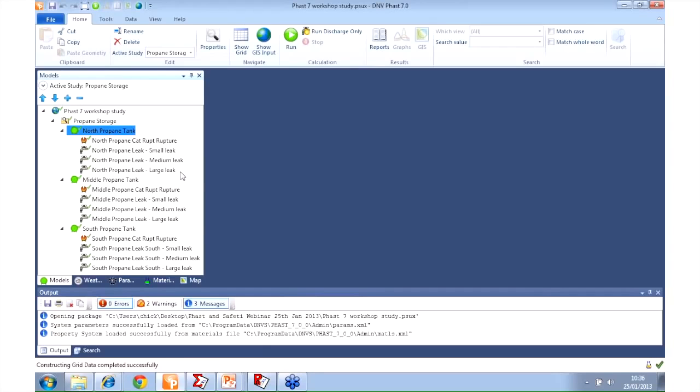If this was an atmospheric storage tank, you could look at venting from the tank while the vessel was being filled, things like this. So, just from what I'm saying there, you can see catastrophic ruptures, major accident hazard with a high consequence and a low frequency. Venting from vapor space, that's a kind of hazardous area classification problem, that kind of thing, and that's a low consequence, high frequency event.